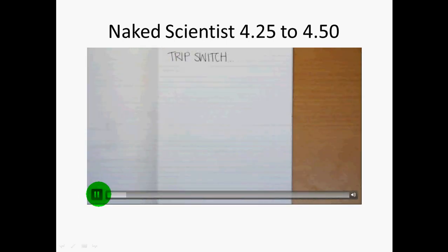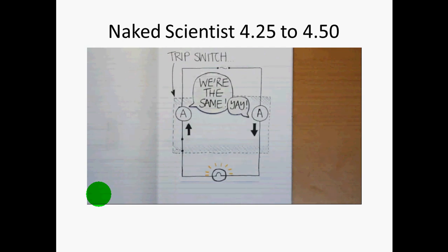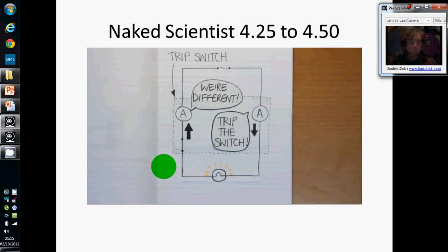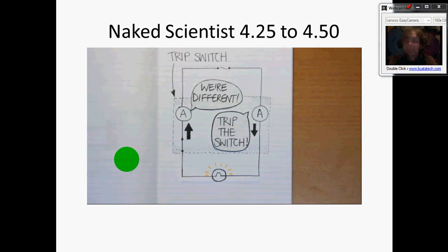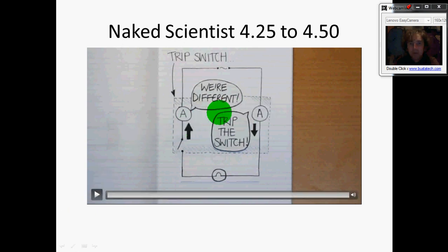Trip switches compare the currents in the live and neutral wire. When everything is working normally, they should be the same — so it's all balanced. But if you touch the live wire, a small current would flow through you to earth, so more current will flow in the live wire than the neutral. This unbalanced current is what the device detects, and it quickly cuts off the supply. The idea is about monitoring the difference on either side — if there's a difference, it means some current is leaking out somewhere, which could indicate somebody getting an electric shock.